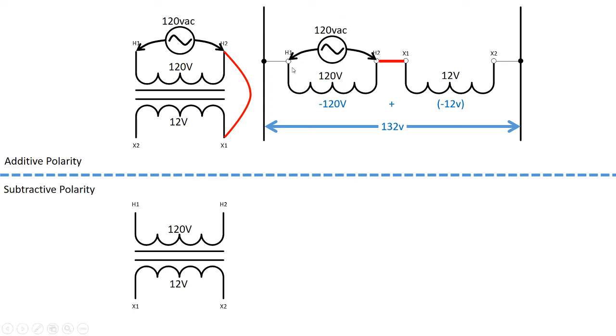You can see why we call this an additive connection because this coil of 120 volts plus the potential induced voltage of this coil gives us an additive voltage of 132 volts. And if we were to take a voltmeter and plug it in over here H1 to X2, that's what would indicate—that's what our meter would indicate is 132 volts AC. So that's our additive connection.